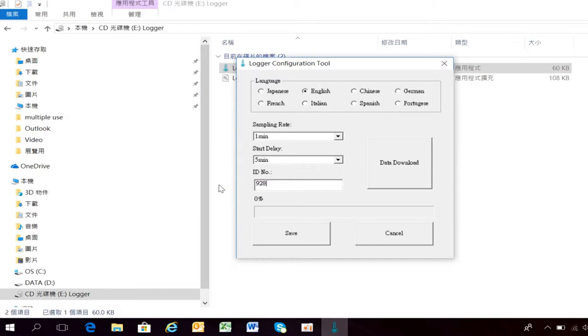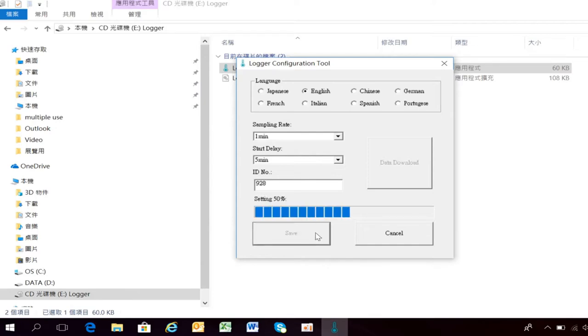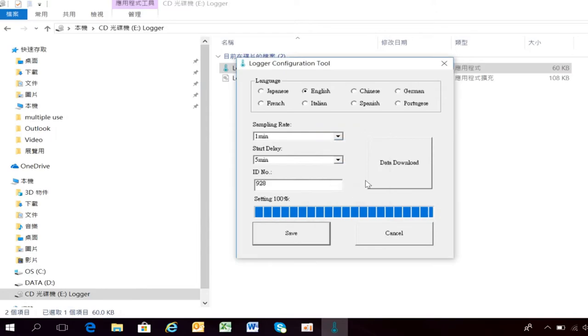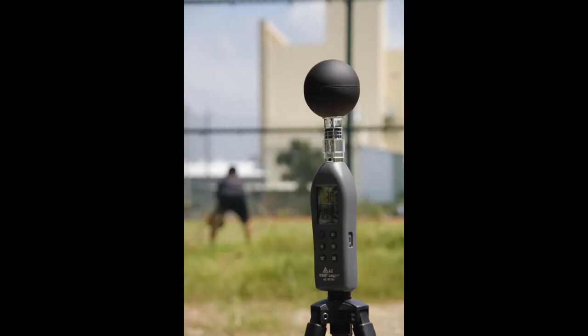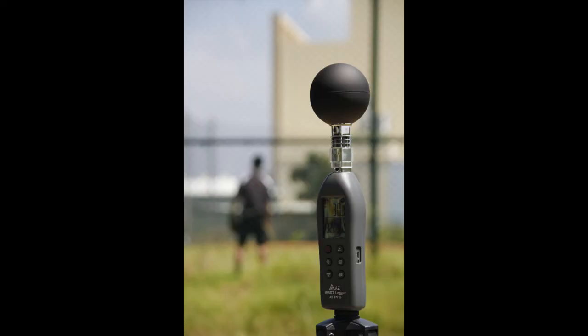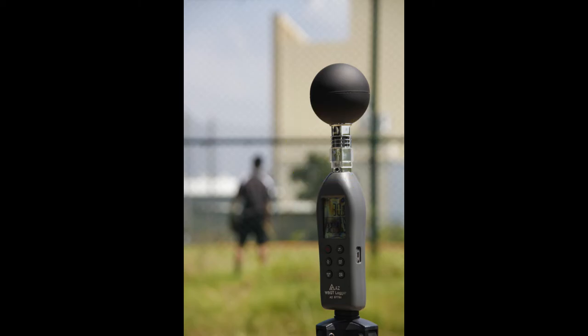After setting, click Save to synchronize the settings and your computer time to the WBGT Datalogger. Close the setup screen, then disconnect the logger and leave it at the place where you want to monitor the heat stress condition. Remember to slide down the transparent protection shield to speed up the humidity response.